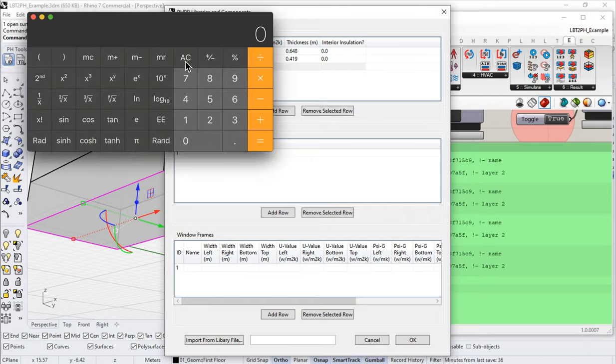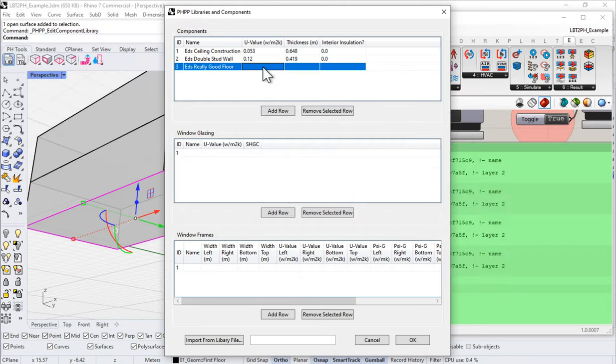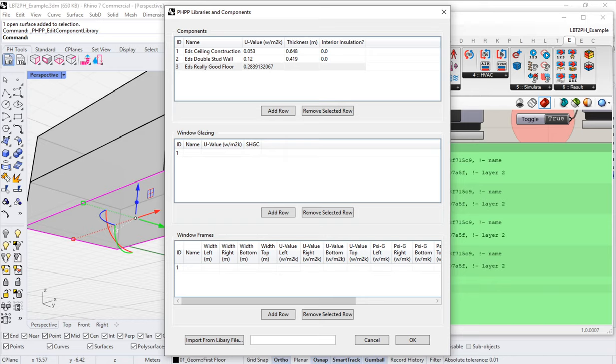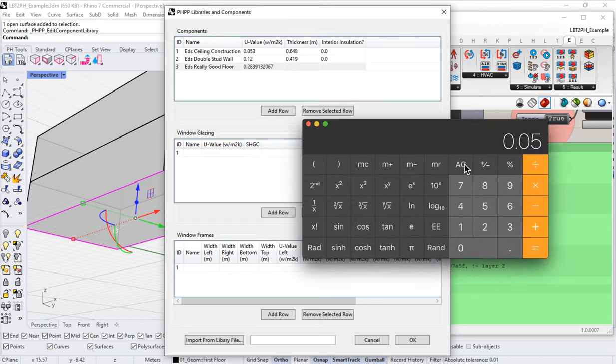Let's say it's going to be an R-20 or R-25 floor. If it's an R-20 floor, one over the R-value gives us a U-value of 0.05. I can enter 0.05 IP and it'll convert to a metric U-value. In the US we commonly work with R-values instead of U-values when working with contractors.